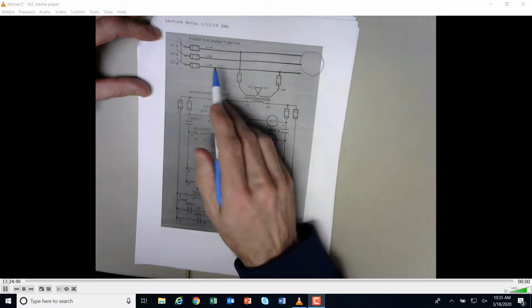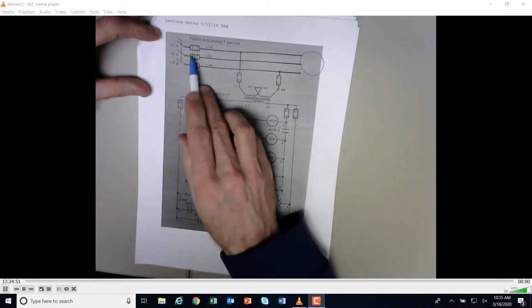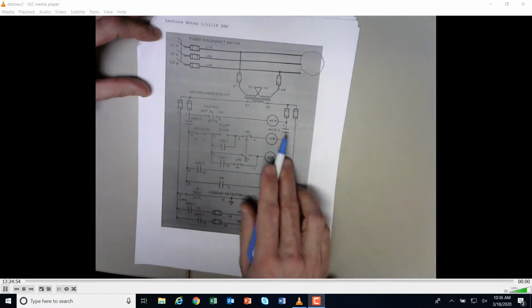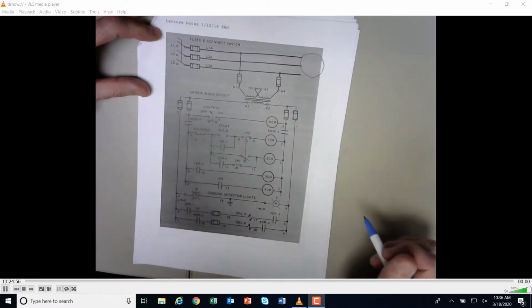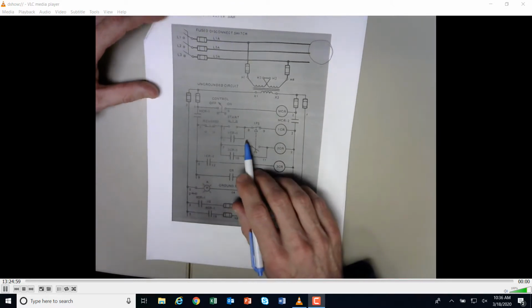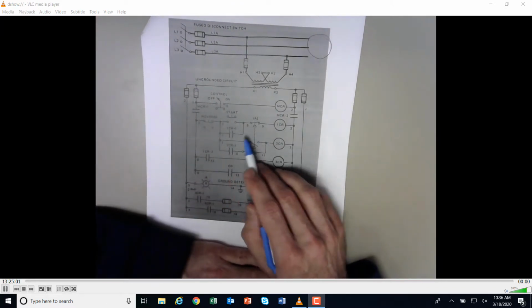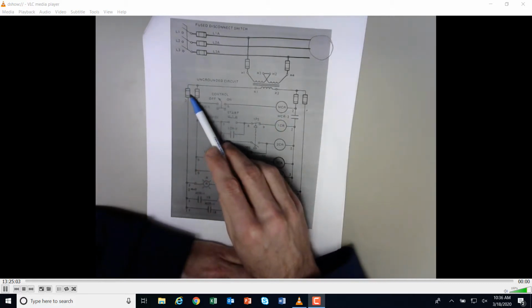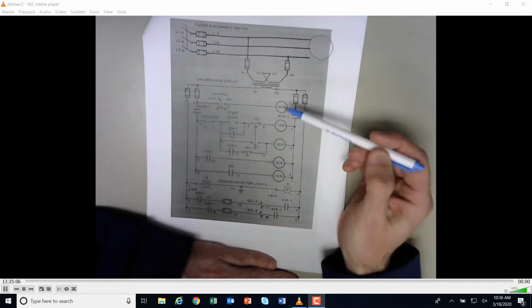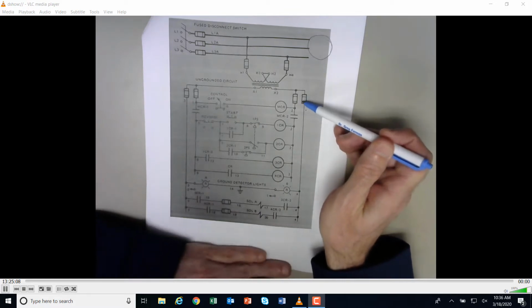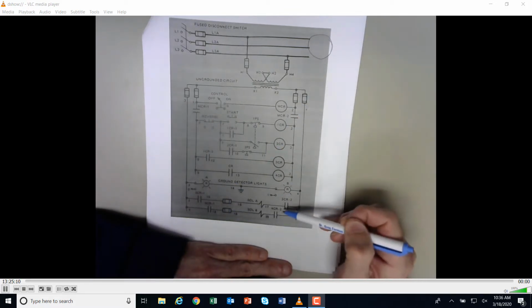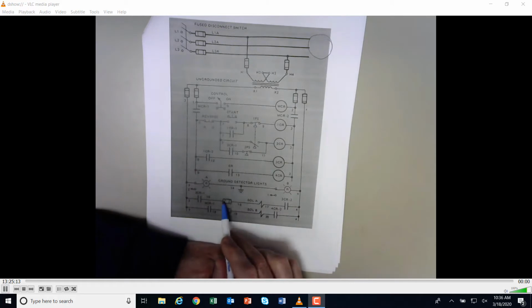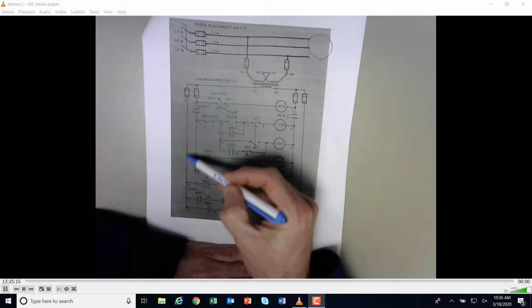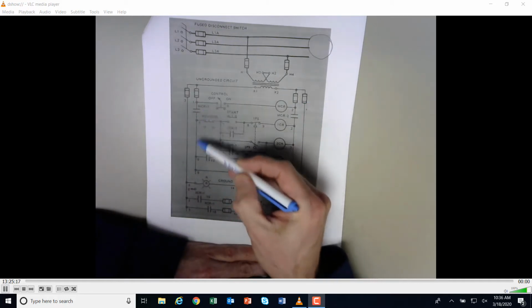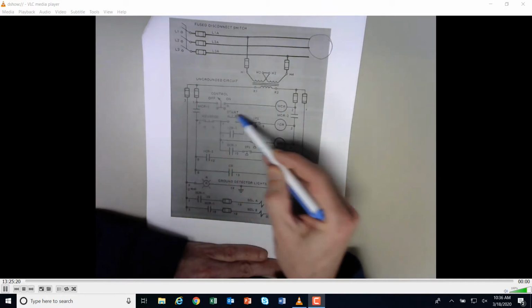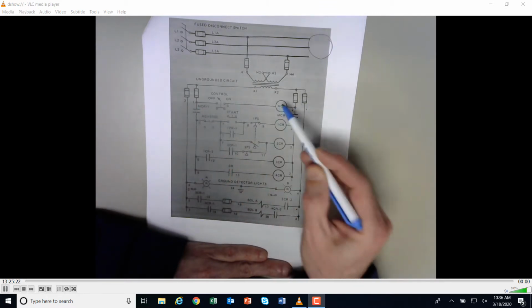Well, let's say these fuses are not going to blow because of operation that's occurring here in the control circuit. In the control circuit, fuses are going to blow because you've got a short here. So notice we've got other fuses going on here. The way that these fuses work is we've broken out individual rungs with their own fuses. We've got different rails that have their own fuses. And then we've got, I guess, our main master control relay rail with its own fuses.